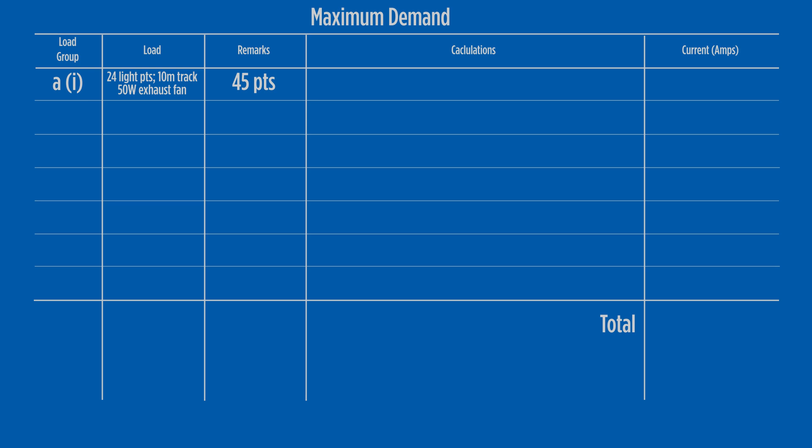Let's apply the calculation from column 2 of table C1. The first 20 points attracts 3 amps, the second 2 amps, and the remaining 5 points add another 2 amps. This gives a total of 7 amps for load group A1.